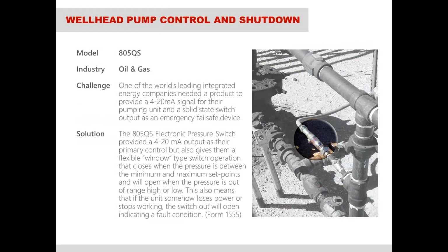Wellhead pump control and shutdown. The 805QS can actually be used as an interlocking system, so that if the pressure gets too high or too low, you can use the switch feature to shut down the well and force the operators to go out there and check the transmitter and check the situation. The only way to reset it is to go into the transmitter itself and reset it manually. That way it forces the operators to go out there and make sure they solve the problem before they turn everything back on.